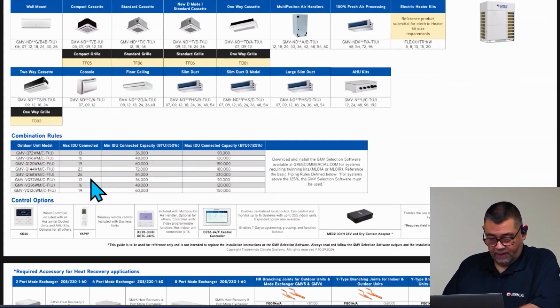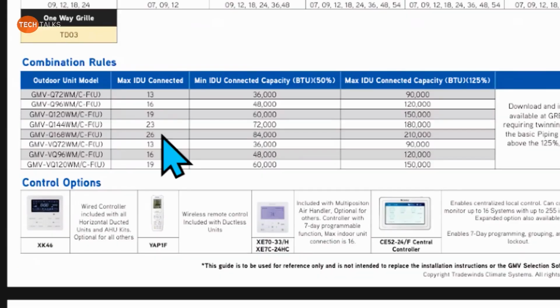And to reiterate Greg's point here, on this particular 14-ton unit where my mouse is, it shows the maximum indoor units is 26. That 26 doesn't mean it's all 18K indoor units. It's all based on the outdoor capacity and the combination of the indoor units. Right, because you're not going to get any more than that. I said, just because you can zone it that much doesn't mean you should.